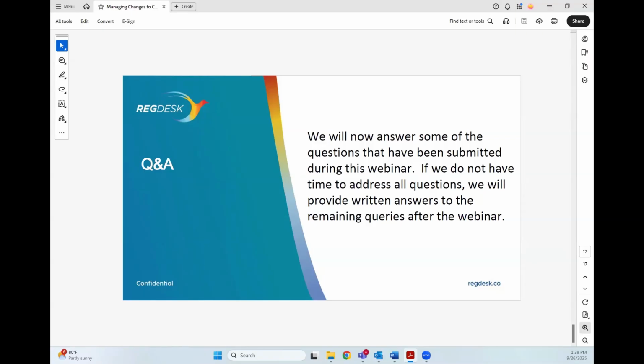Okay, and I just want to add on to that a little bit. That is why the assessment up front and the planning is so critical. You need to understand the typical window for approval of the changes so that your company can plan accordingly. We know that some modifications being made to a product are critical in that you don't have time to wait to make the change. As an example, if you've got a supplier who's providing you a pouch for your product and they are no longer going to be able to provide that to you, they've got a defined cutoff period. That is your sterile barrier on your product. You have to be able to cut over when you run out of supply. So making sure that you understand the landscape in each country, and at least a ballpark for the approval timeframes, will help set your change control and your company up for success.